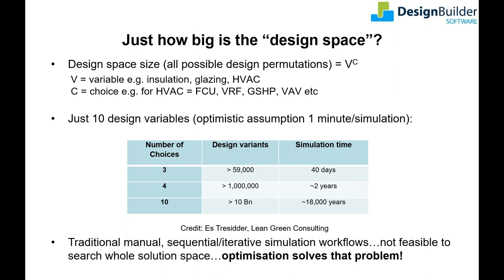For each variable you'll have a number of choices. For example in your HVAC system you may have identified fan coils, VAV systems with traditional boilers and chillers, VRF, or ground source heat pump — that's four HVAC system choices. If we include a total of 10 design variables with only four choices each, the table shows that results in over a million possible design permutations. Manually assessing even just one relationship between a small number of design variables takes a huge amount of time. This is why design teams have previously been forced to resort to what works based on past experience and rules of thumb. The answer to this problem is design optimization.